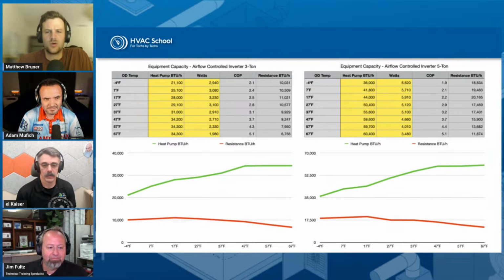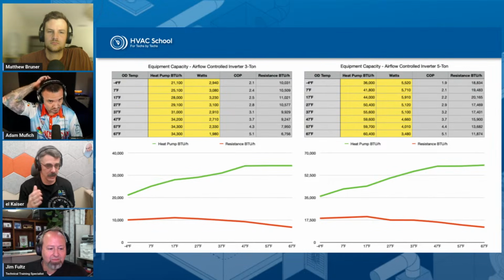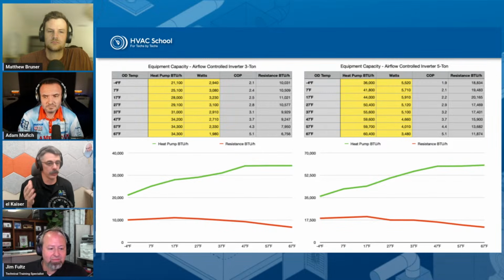Gotcha. So walk us through these. What are you wanting to show here? So with both of them, I'm showing the performance. If you look up at the top graphs, on the left side, we've got your outdoor temperature. Next to that, we have our corresponding heat pump BTU output. At that outdoor temperature, we have the wattage that's being drawn by that heat pump to produce that amount of heat. And then to the right of that, we have our COP column, which is our coefficient of performance. So if you look at that 3-ton up there at -4 degrees, it's got a COP still of 2.1.